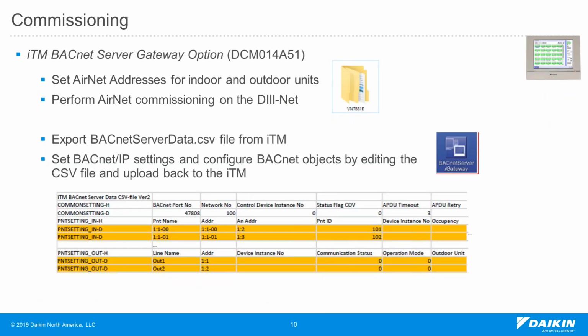For the commissioning of the ITM BACnet server gateway, first you need to perform the AirNet commissioning on the D3 net, which means that you need to set up the AirNet address for both the indoor unit and outdoor unit, and use the AirNet commissioning tool to commission the AirNet on the D3 net. After you configure the AirNet commissioning, you can go to the ITM and export the BACnet server data commissioning file from the ITM. It is just a CSV file that you can easily edit with Microsoft Excel. In this configuration file, you set up the BACnet IP settings, the instance numbers, and you can select which individual BACnet points you want to expose to the BMS here.